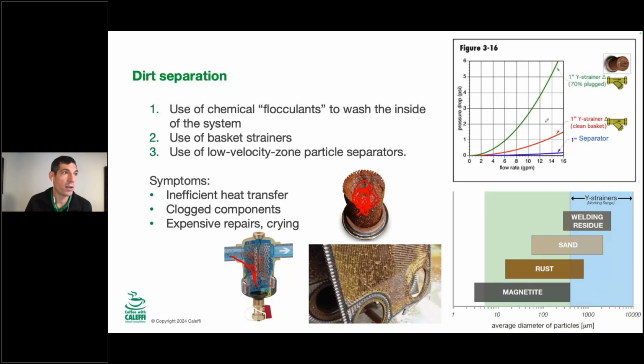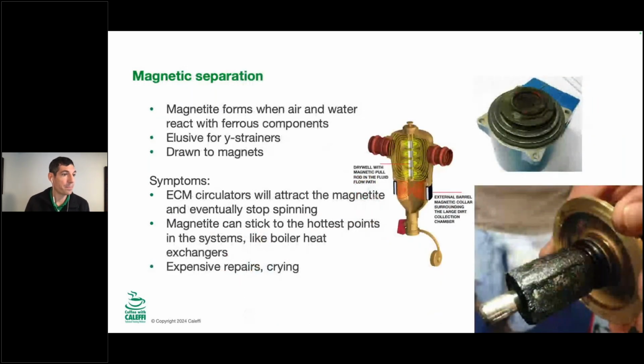So you're always trying to pump past a growing number of things that are blocking your Y strainer. As a Y strainer becomes 70% plugged, look at how much pressure drop you've added to that system. In this case, if we're at 14 GPM and it's 70% plugged, we've added 5 PSI to that pressure drop across that device, which is really going to affect the flow rate that you need for the system or for the boiler, if that's the case. You can also get much smaller debris out with a dirt separator, down to the diameter of your hair, that would go right through the basket of a Y strainer, but eventually will hit and collide and fall down to the bottom of a dirt separator.